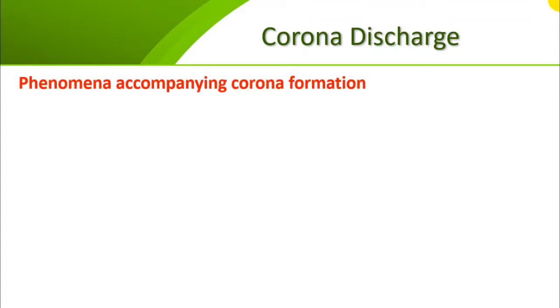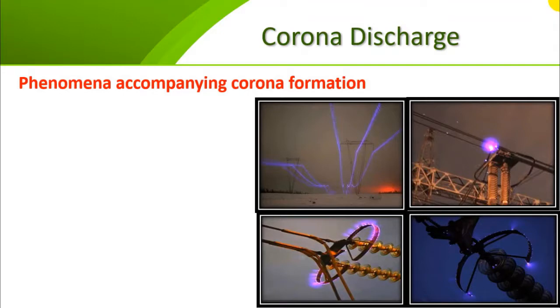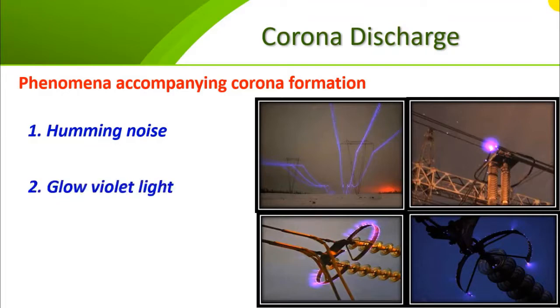When corona occurs, there are various phenomena accompanying corona formation. First, when corona occurs, you will hear a humming noise. This noise happens due to the ionization of the air near the conductor. When the ions of the air need to be neutralized again, it creates a pressure wave in the form of humming noise. Also, when corona occurs, you will see a violet glow near the conductor. This is of course due to the ionization process of the air atoms. When free electrons are liberated from the atom, it emits energy in the form of photons, which can be seen as a violet glow.